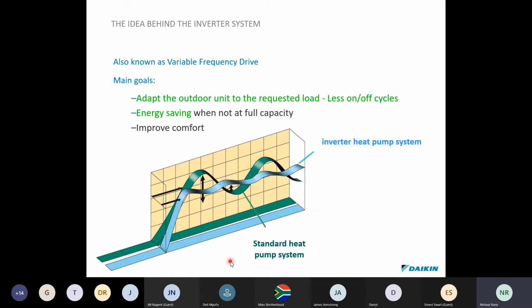So the inverter control, also known as the VFD, which is a variable frequency drive. And what is the main goal of it? It is to adapt the outdoor unit to the requested load. That's what the inverter is. So before, when we had non-inverter technology 30 years ago, you either had bang on, bang off. So you had maybe two compressors, so you had 100% capacity, 50%, and 0%, obviously when it switched off. You could have had a two-stage compressor. Maybe you'd have had 4 points.